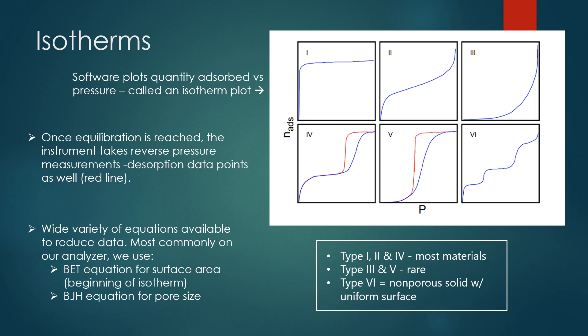These different types of isotherms are determined by how the material is physically characterized. Type 1, 2, and 4 are what we see most often. Type 3 and 5 are very rare, and Type 6 is a non-porous solid with uniform surface, which is also very rare. The two most common types of data reduction equations we use are the BET equation for surface area and the BJH equation for pore size, but there's actually a wide range of data reduction techniques you can use to deduce data in a variety of ways.